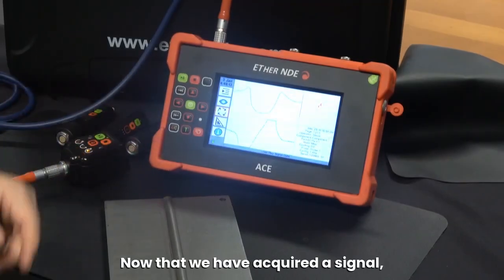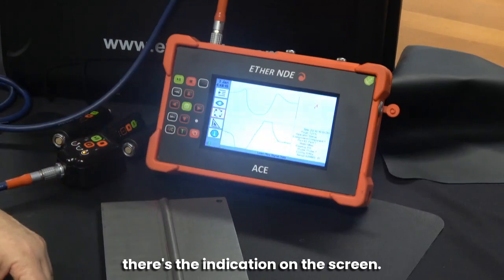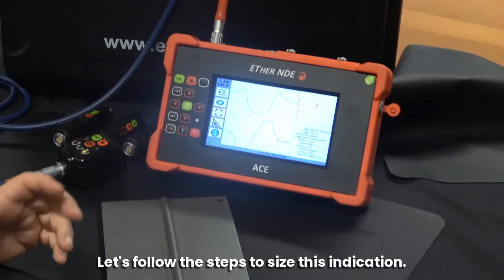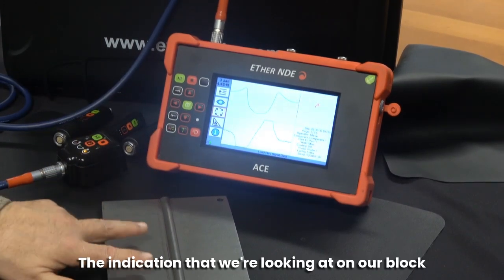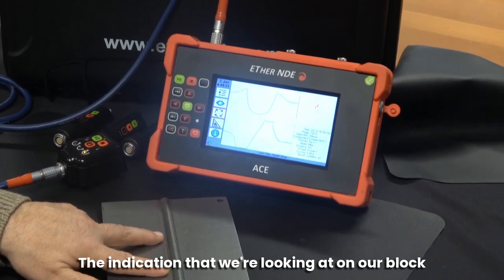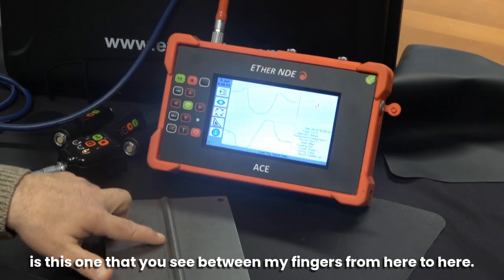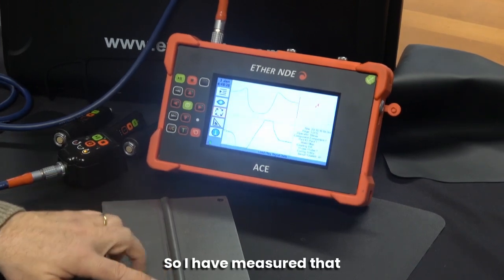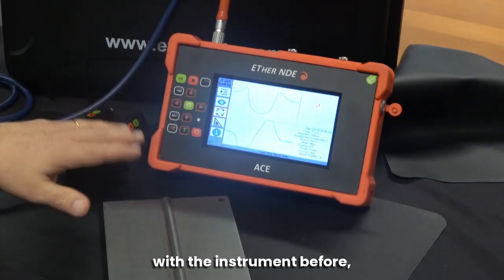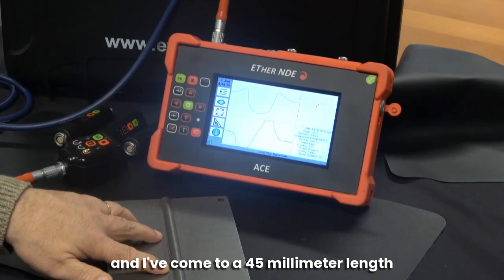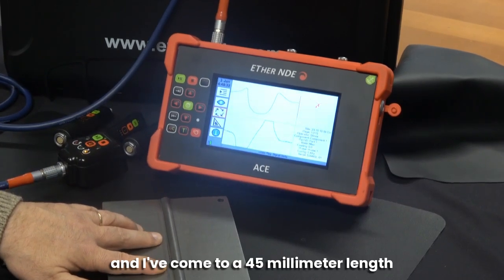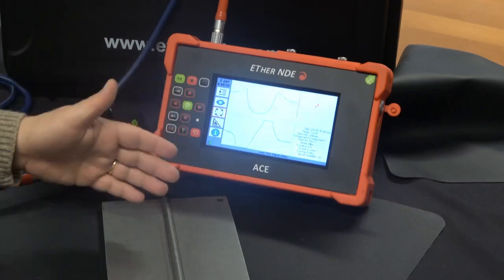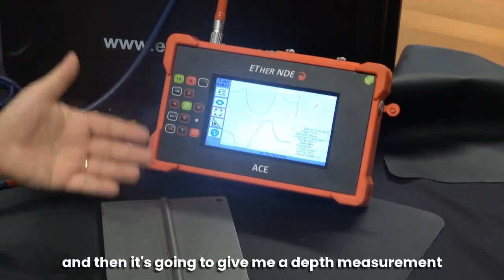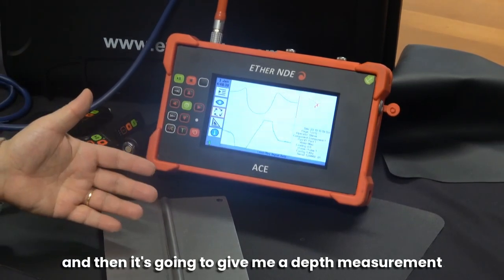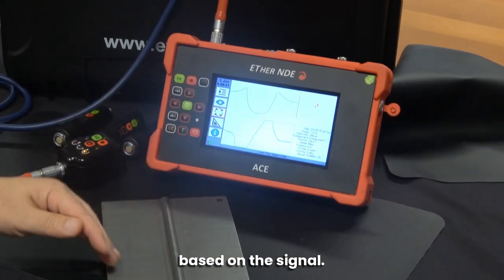Okay, now that we have acquired a signal, there's an indication on our screen. Let's follow the steps to size this indication. The indication that we're looking at on our block is this one that you see between my fingers, from here to here. I have measured that with the instrument before, and I've come to a 45 millimeter length. Now I'm going to input that, and then it's going to give me a depth measurement based on the signal.